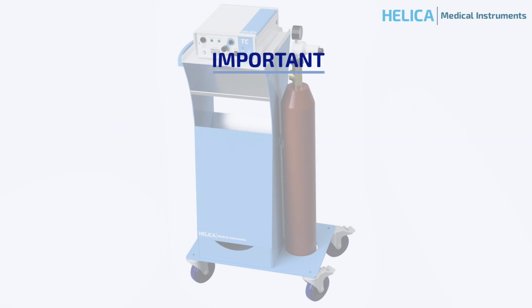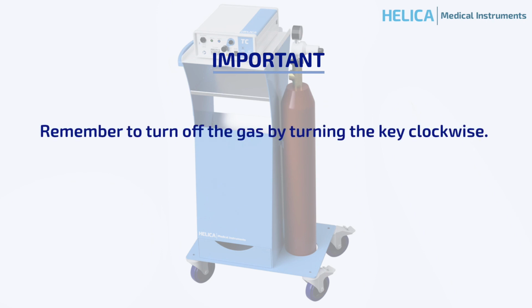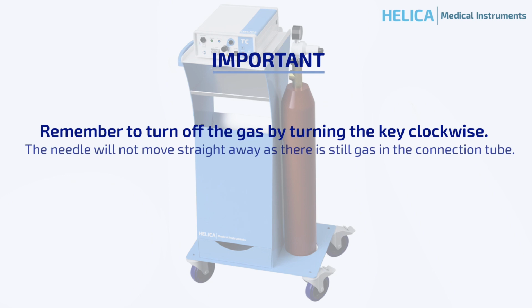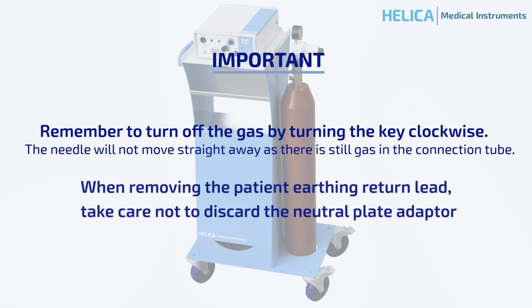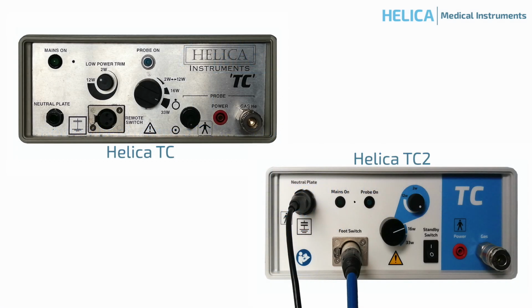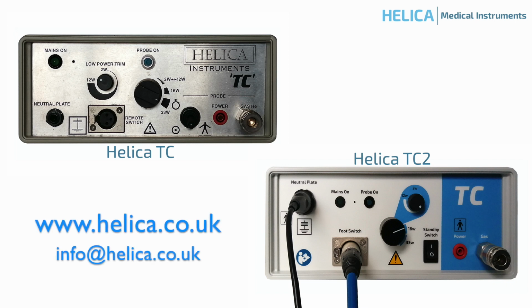Two important points when the procedure is completed. Remember to turn off the gas by turning the key clockwise. The needle will not move straight away as there's still gas in the connection tube. Secondly, when removing the patient earthing return lead, take care not to discard the neutral plate adapter, magnetic on new machines. The Helica is a robust and reliable device, but if there are any issues, please contact Helica for prompt service from one of our engineers.